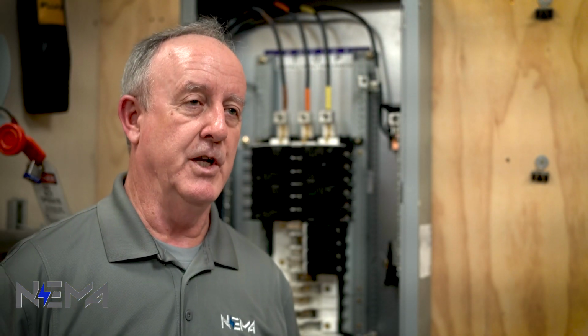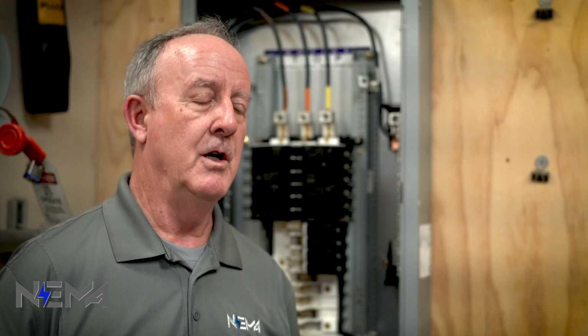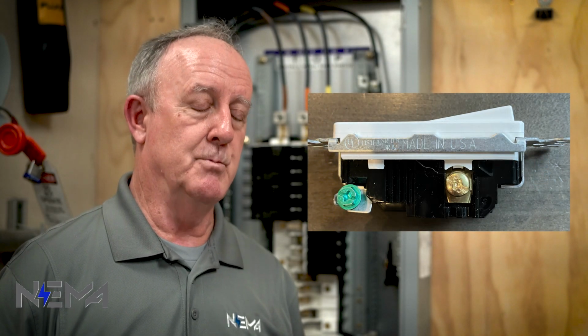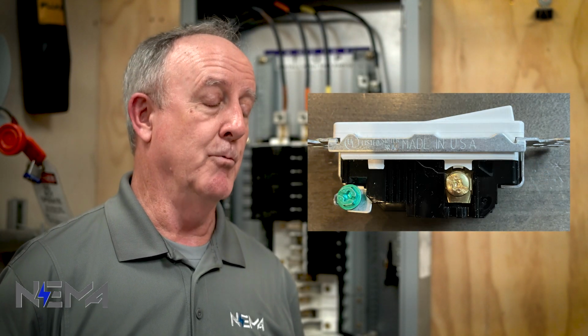So conductors can be copper, aluminum, copper-clad aluminum. They can be solid, stranded, or compact stranded. But the same torque values apply to all conductors. It doesn't matter what type of conductor they are. And you can have different types of connectors. You can have set screw connectors. You can have wire terminals like you see on wiring devices or some smaller circuit breakers. You can have wire binding screws on smaller devices. But regardless, the manufacturer's instructions need to be followed.